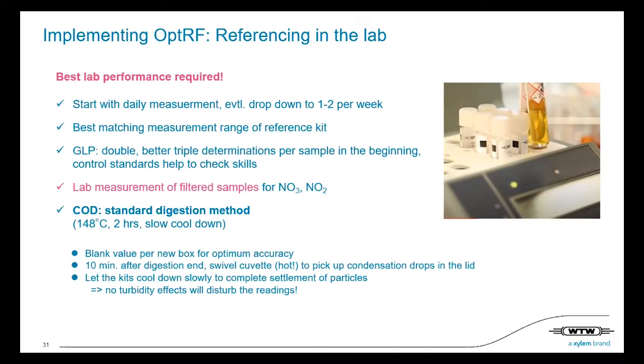I mean, we know it from routine analysis that we should do that, but actually also for user calibration of optical reagent-free, it's the same importance as for daily measurement. I skipped the doubling—you are doubling and tripling tests. And then also, as I said, filtered samples and the COD standard digestion measure should be performed very well. So it's worthwhile to make a blank value, depending on how long you have the kits, or for each new box.